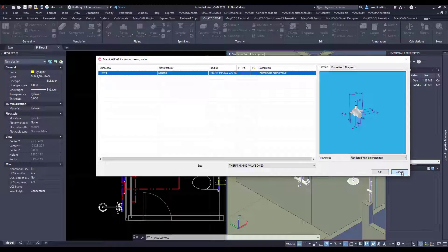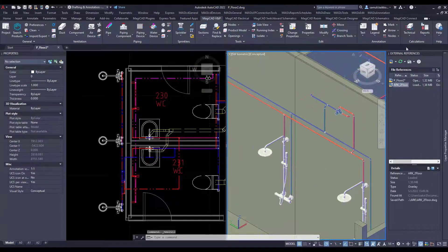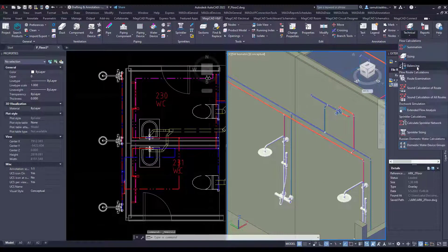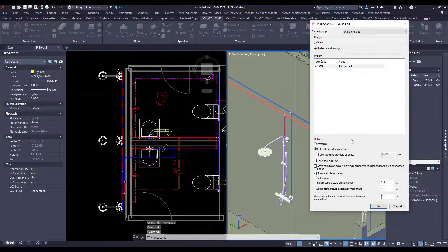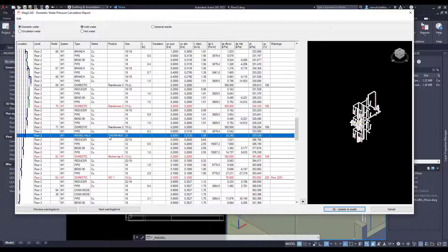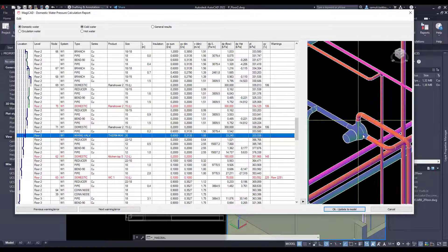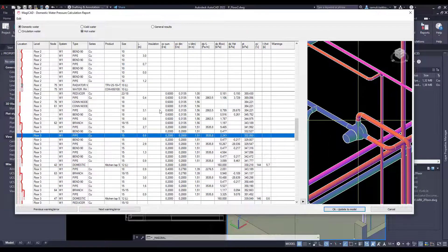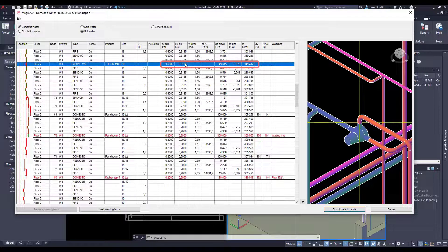Let's perform some calculations. Sizing calculations ensure that the pressure drop or flow parameter is inside the defined limits, so the mixing valve is also taken into account. In my example I skipped the sizing and performed balancing directly. As you can see, all pressure drop values are calculated correctly, both on the hot water side and on the cold water side.